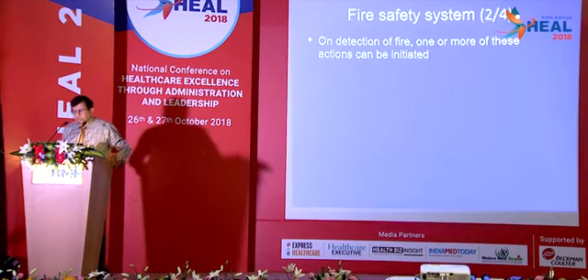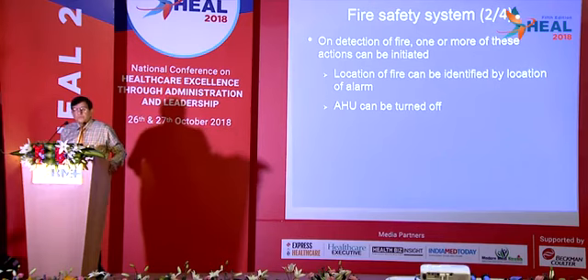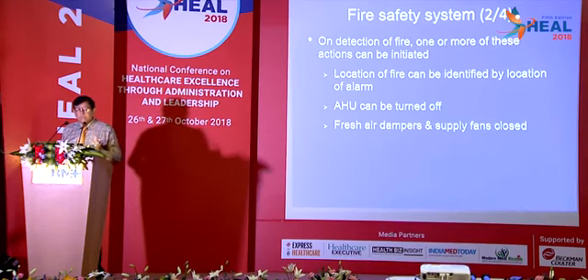On detection of fire, one or more of these actions can be initiated. So you can detect the fire while sitting in the office. We can see the location of fire in a multi-storied building. It becomes very, very easy. We can identify by location of alarm while sitting in the office. The concerned air handling unit can be turned off, otherwise the fire will rush through the air handling unit in the duct. The fresh air dampers and supply fans can be closed. More air, the fire will further become more aggressive. We can unlock all doors, provided access control is also a part of the building management system.